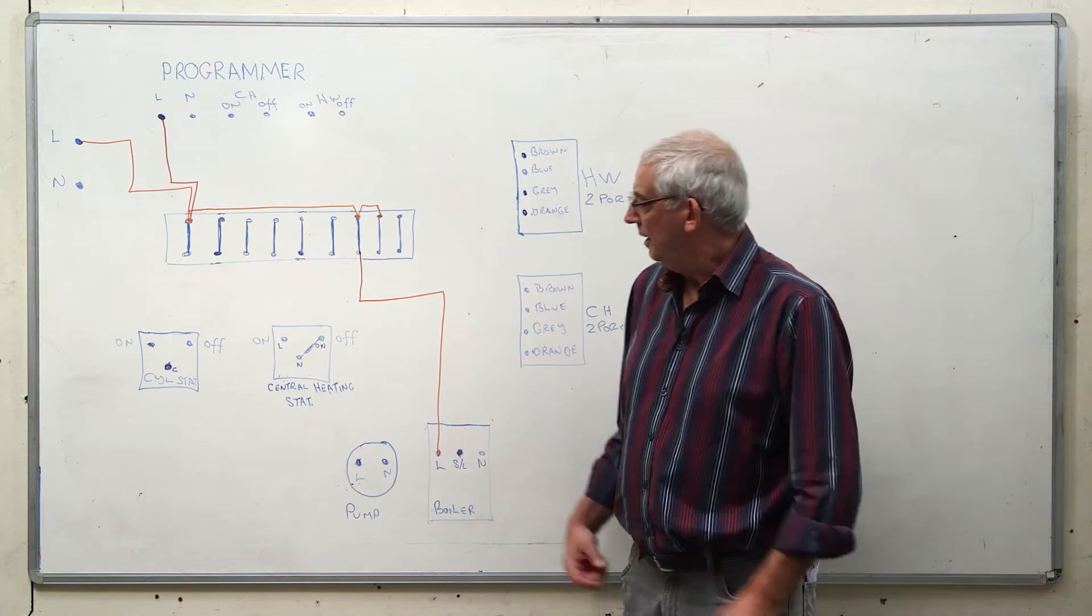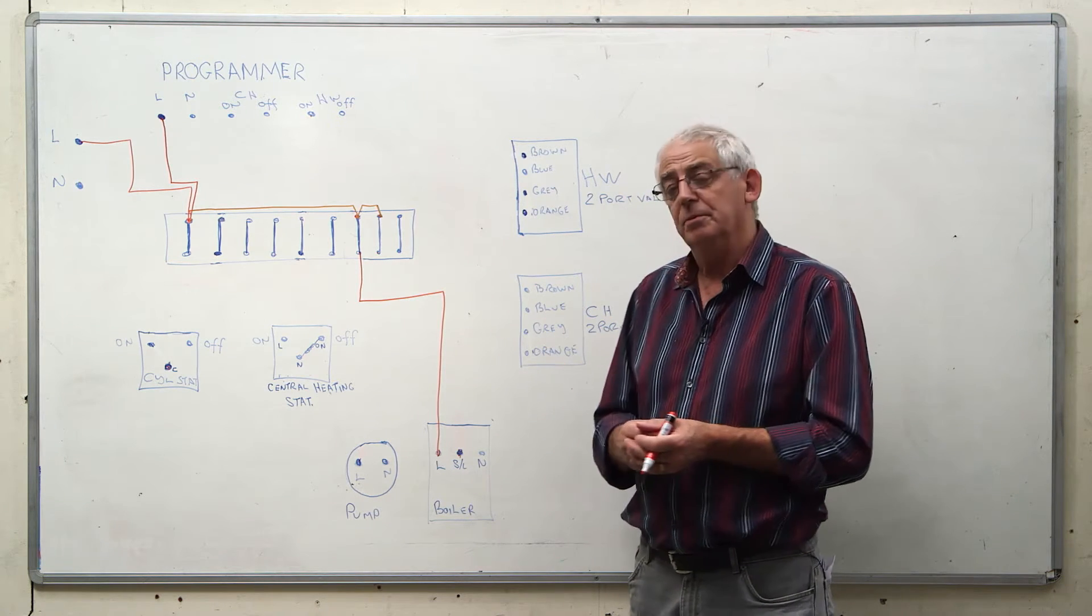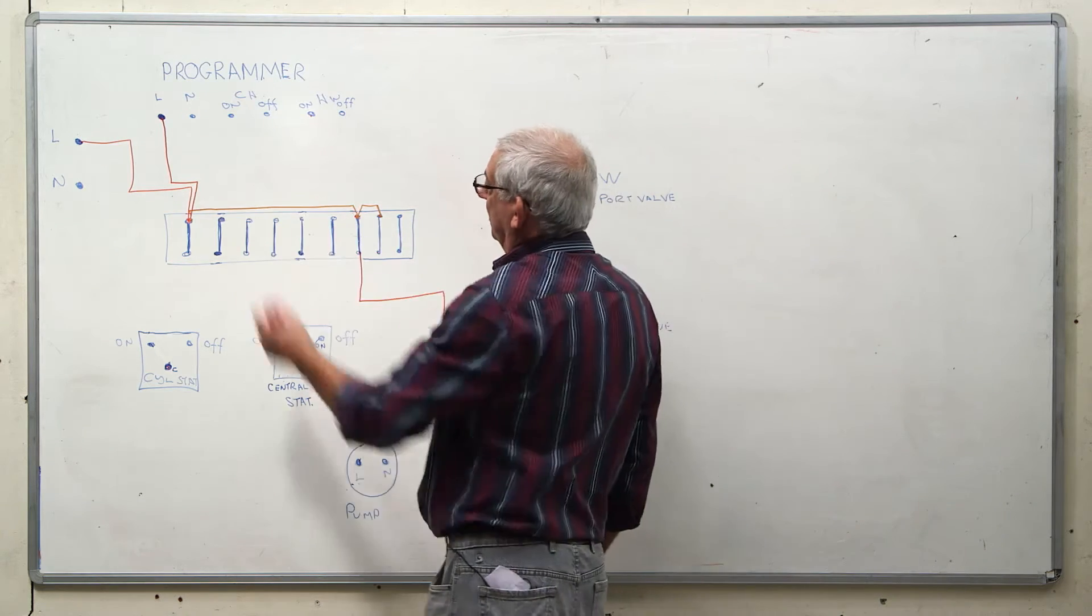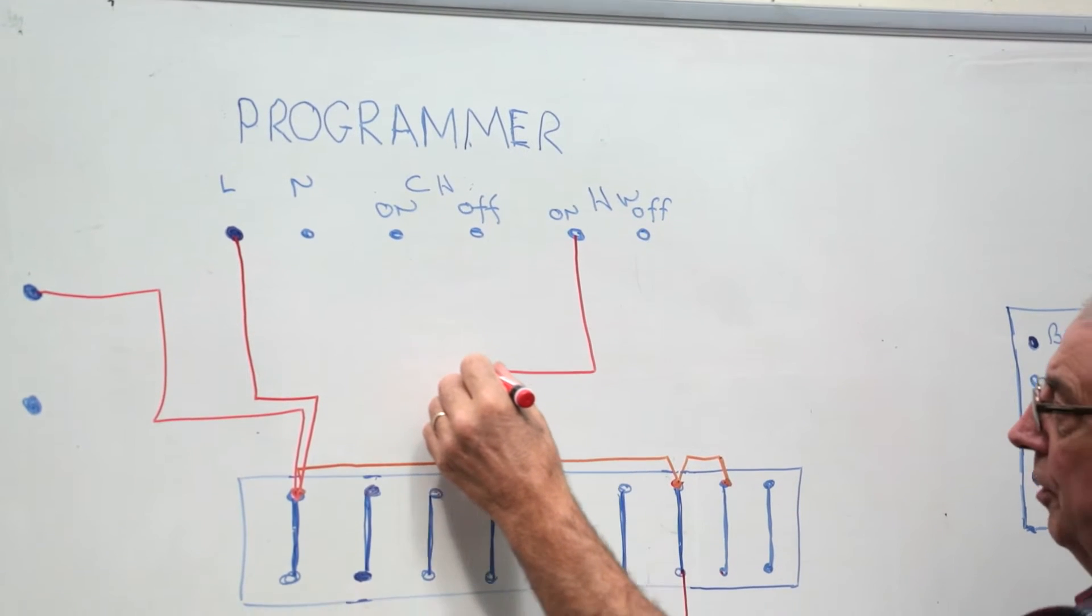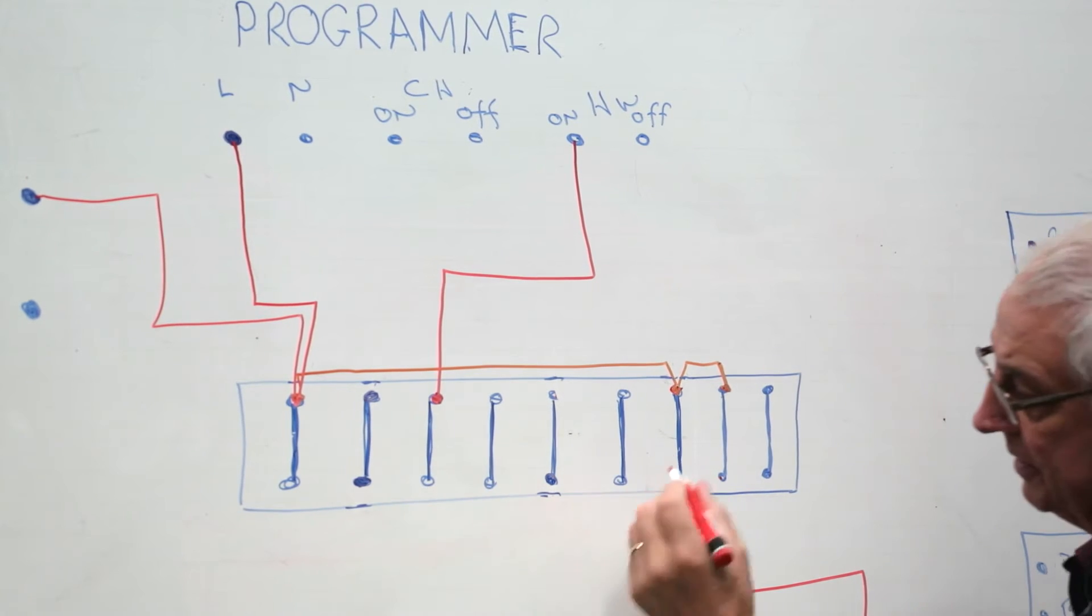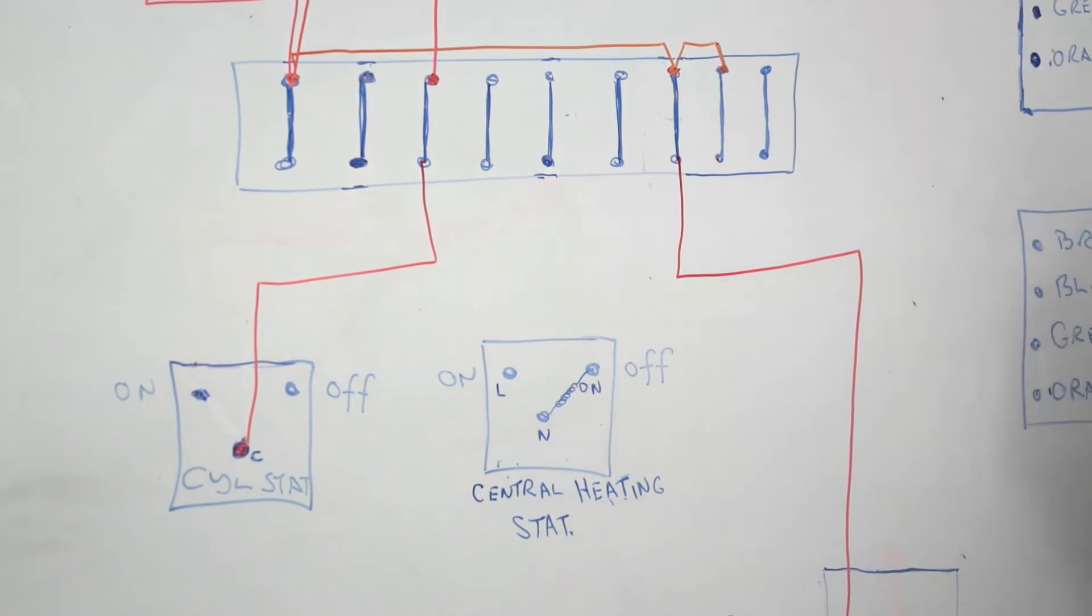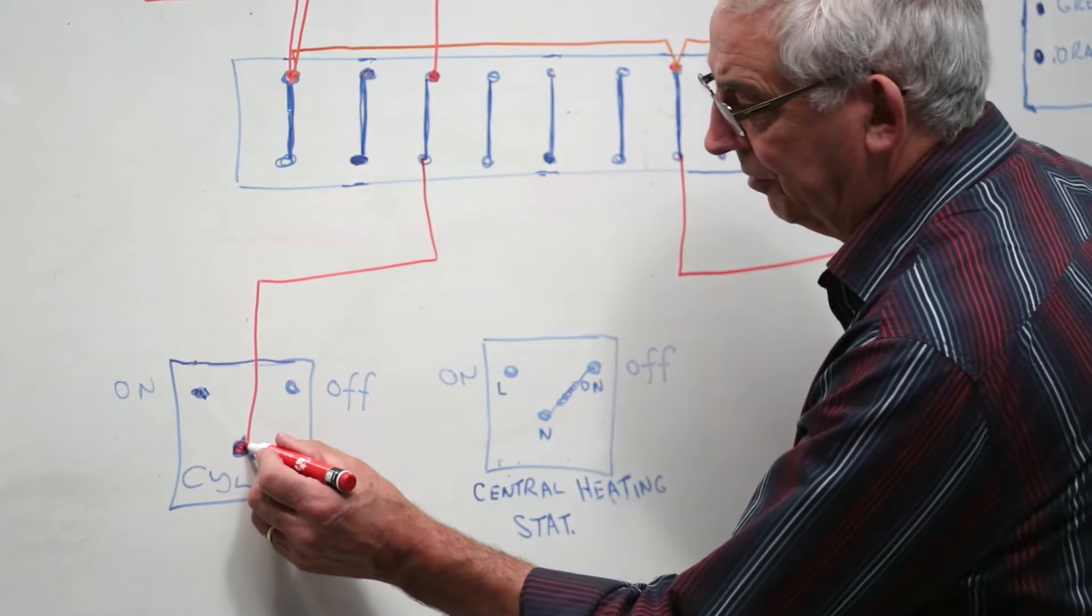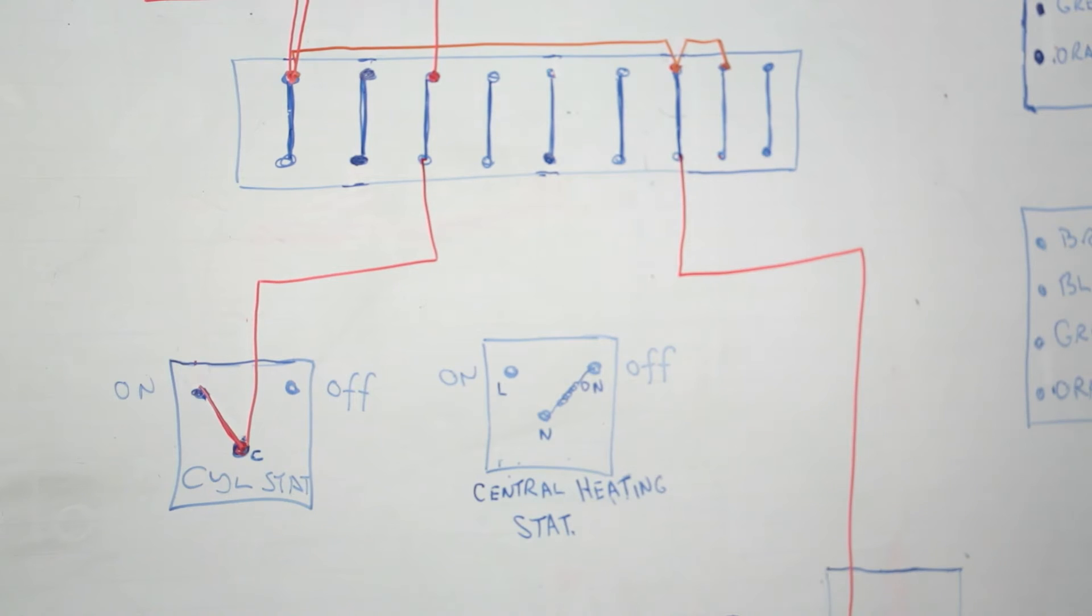Okay so let's just say then that we're switching the system on and the first thing we want to do is call for hot water. So I turn the programmer on, the programmer now calls for hot water. It sends a signal to the common of the cylinder stat. The cylinder stat is calling for heat. So obviously the on terminal now becomes live.